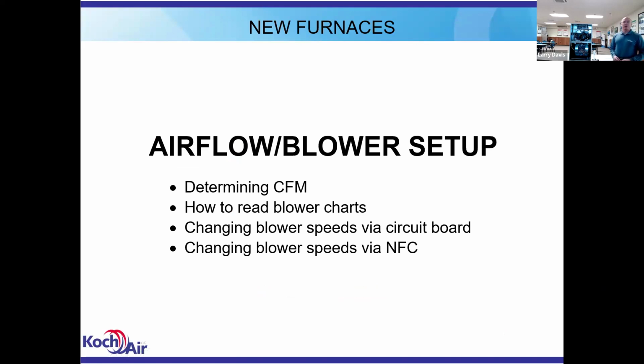So let's talk about how we set the airflow and the blower. The chart's going to look a little different. It's going to have a lot more information on it than what you saw on the old charts from the previous model furnaces. So we'll look at how we read those, how we determine our CFM, and then how we can change the blower speed either through the circuit board or using the app in the near field communication.